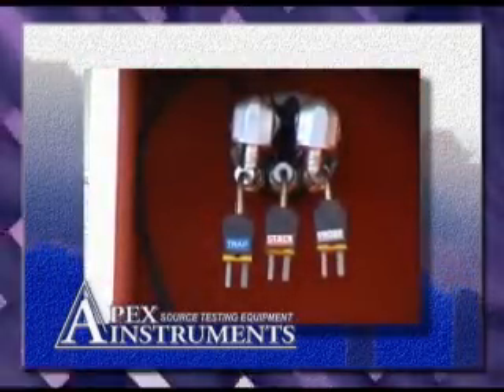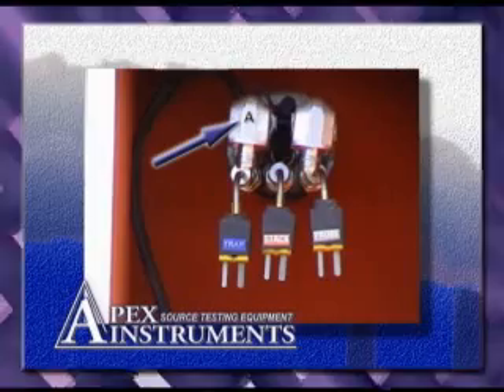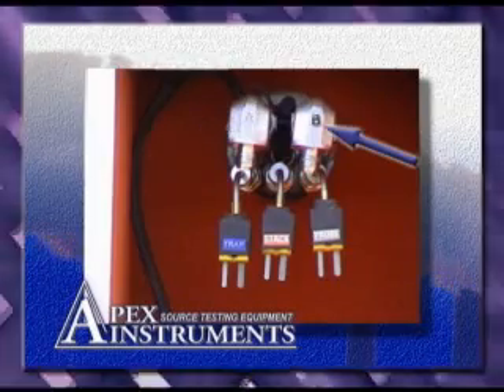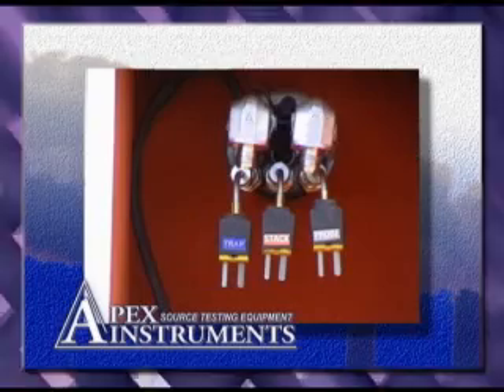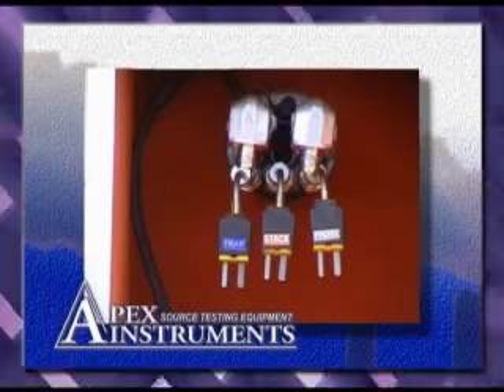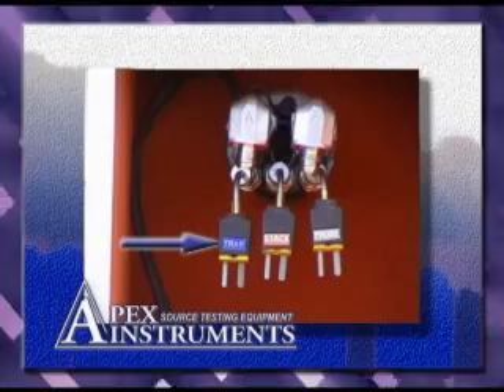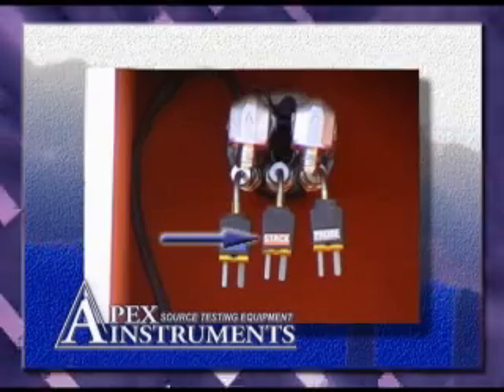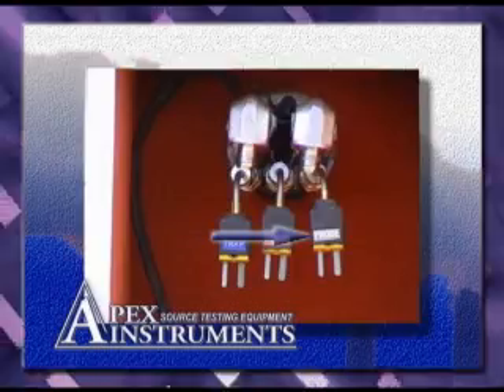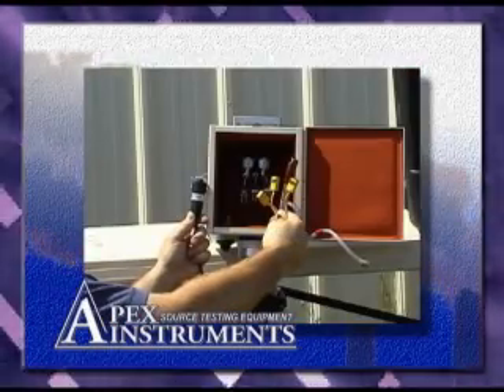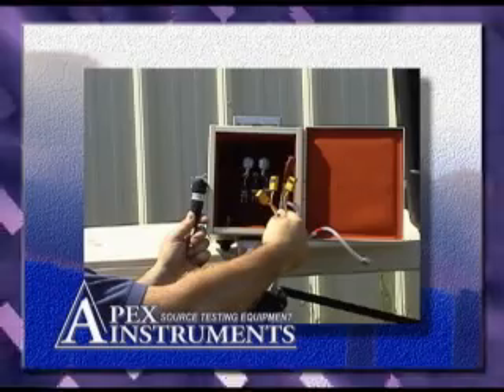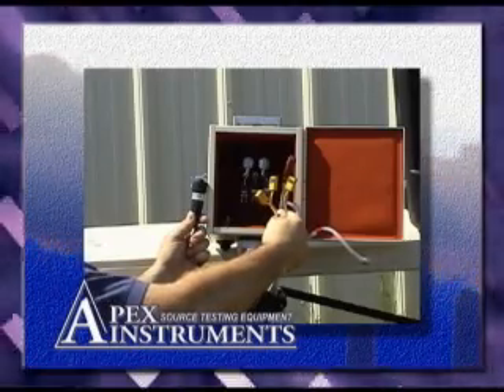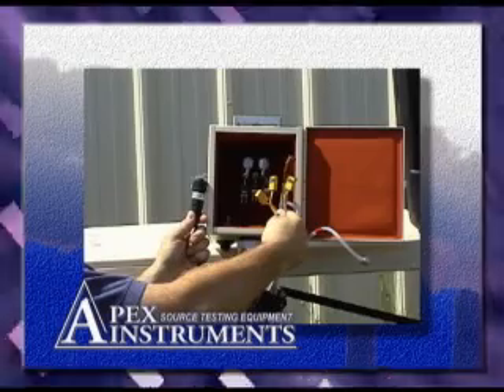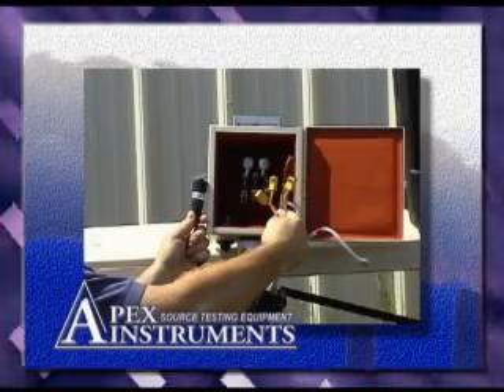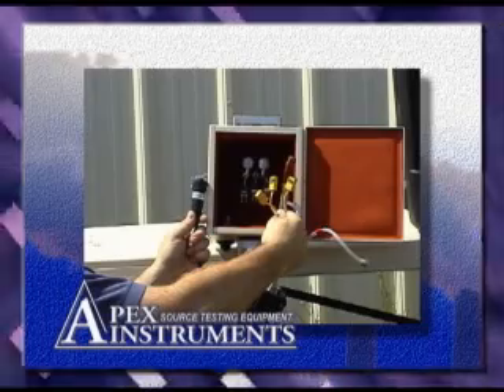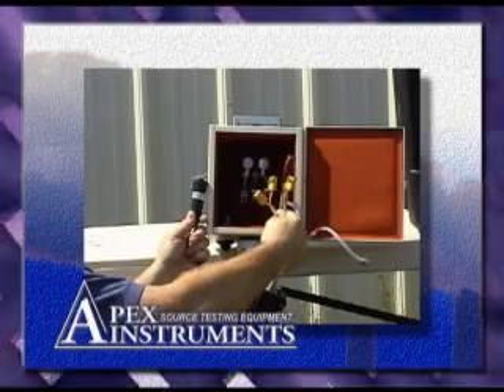There are also two sample line connections, one for the A train and one for the B train, and three thermocouple connections, one for the trap, one for the stack, and one for the probe. The heated umbilical contains the mates for the two sample lines, the three thermocouple connections, the probe amphenol power connector that attaches to the keyed fitting on the probe head, and an extended end of self-regulated heater cable to provide controlled heat in the probe head.